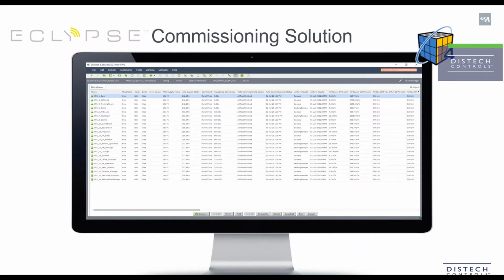ECNet DC commissioning module manages the start of the commissioning process on the selected series of devices. This is done by sending a run command and time delay to selected devices via the ECLYPSE RESTful API. Once the tests are executed using the RESTful API, the module will read test results from the ECLYPSE trend logs, providing you with the timestamp of the latest result. You will appreciate not having to worry about additional licensing thanks to the use of ECLYPSE RESTful API.